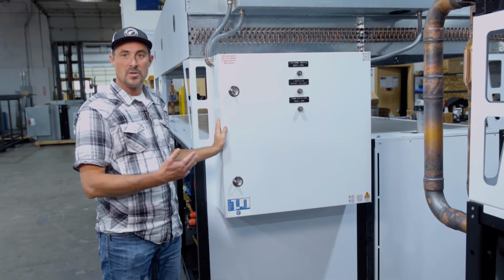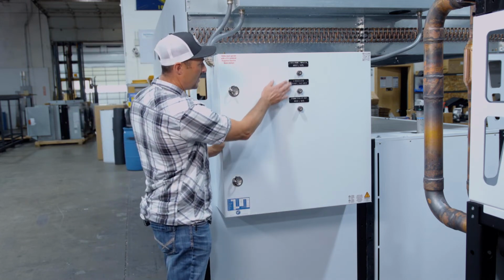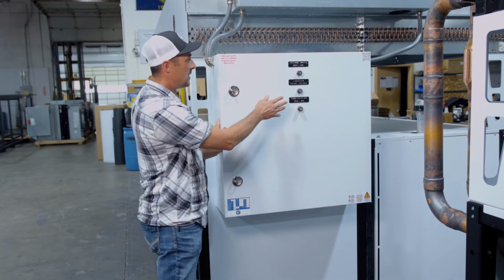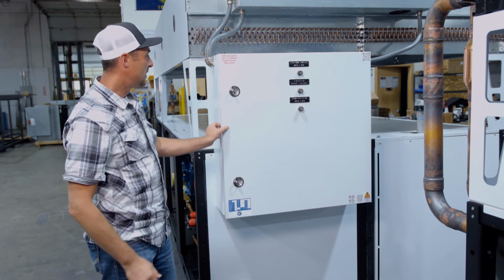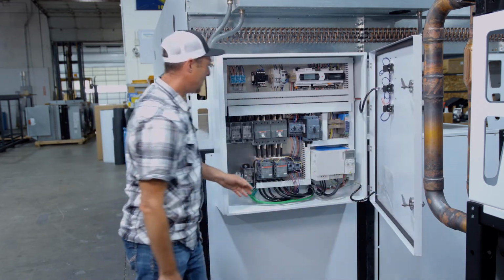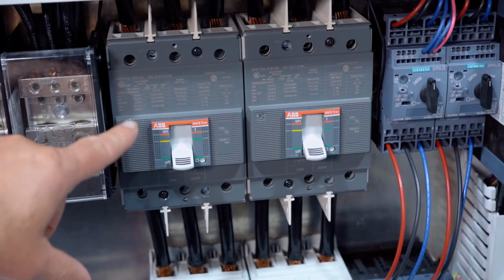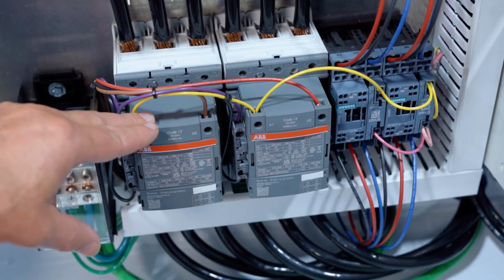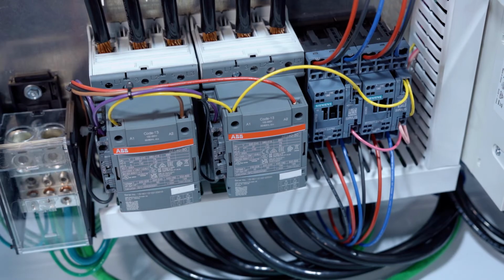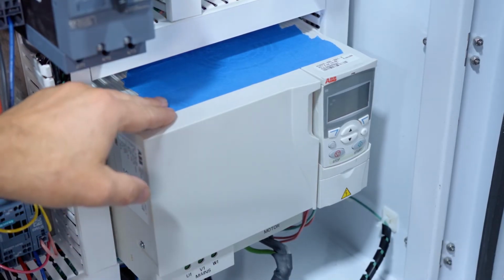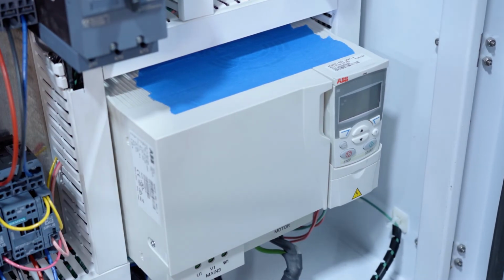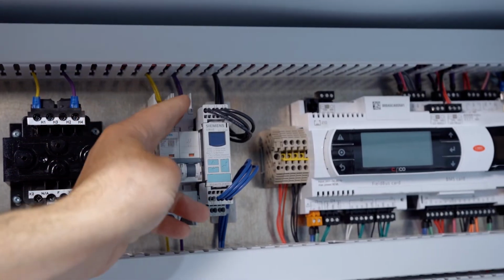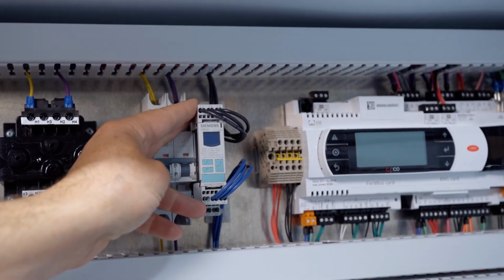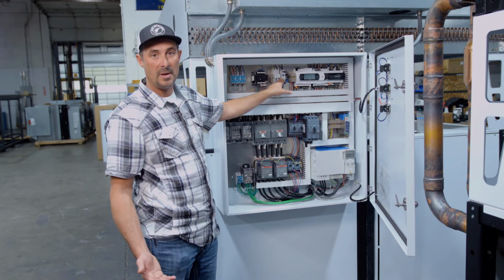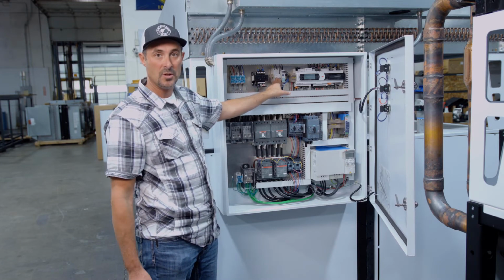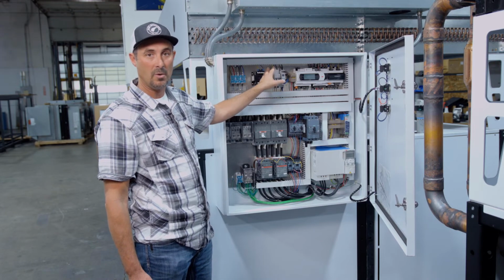I'm just going to go over our simple control panel here. As you can see, we've got three switches here. One is our main control power, and then a couple switches for the different pumps. Inside here, you'll see, again, a very simple design. We'll use circuit breakers instead of fuses. Simple contactors that bring on the compressors and the pump motors. This chiller does have a VFD for the process pump, and along with the VFD for the fans. We also incorporate a phase and voltage monitor. This is important. A lot of our dairy customers aren't going to have the greatest of power, especially in the summer months. This protects the chiller and the motors in the event of a power outage or brownout.